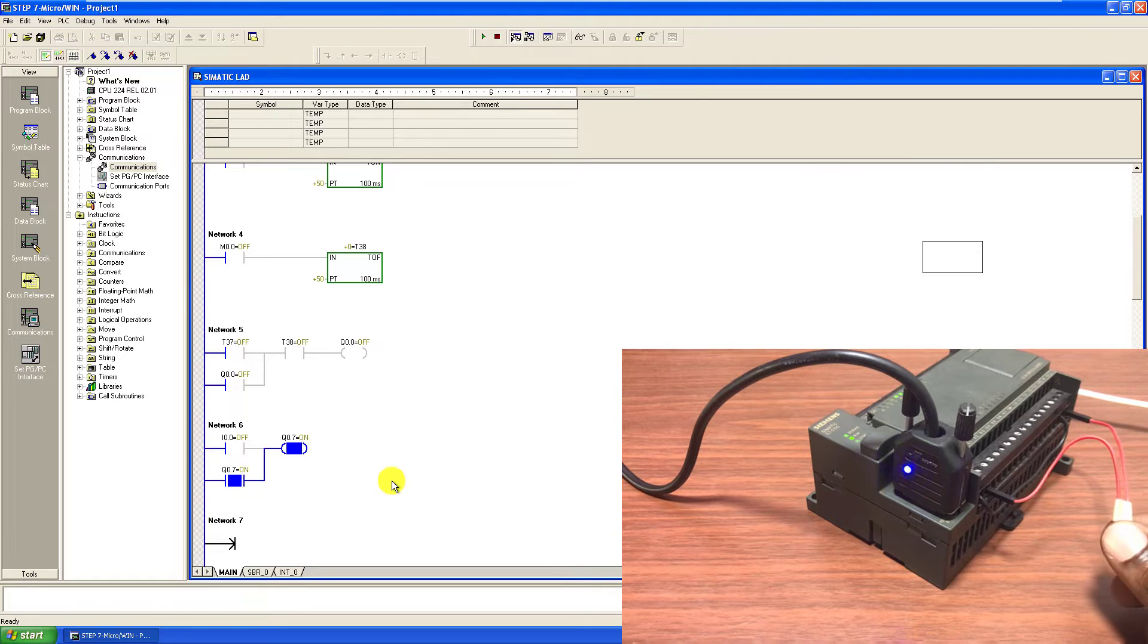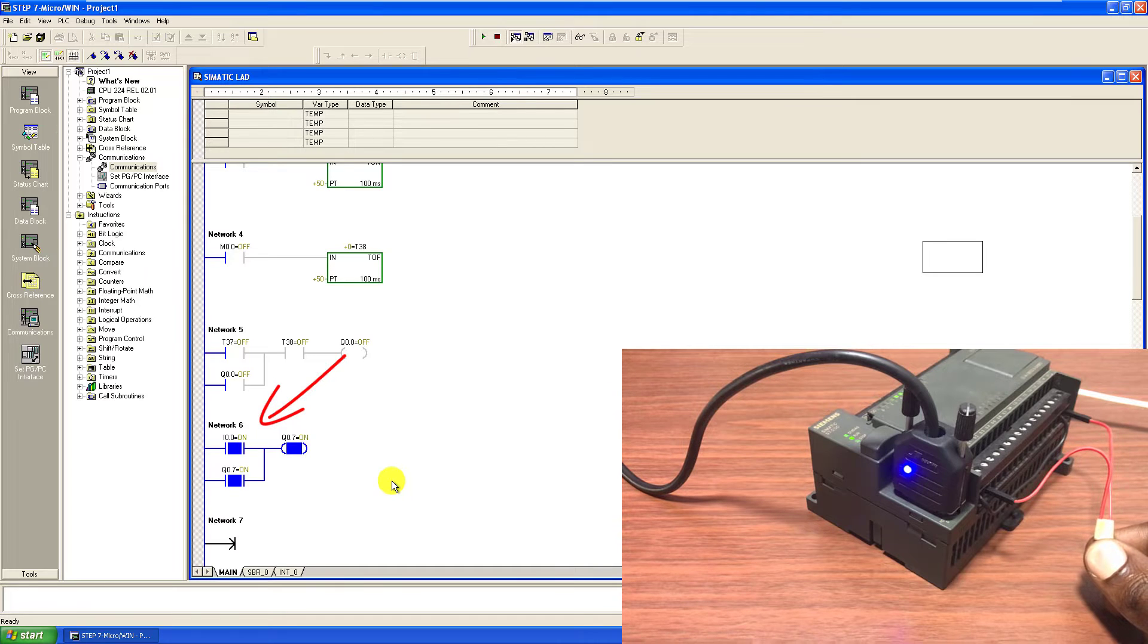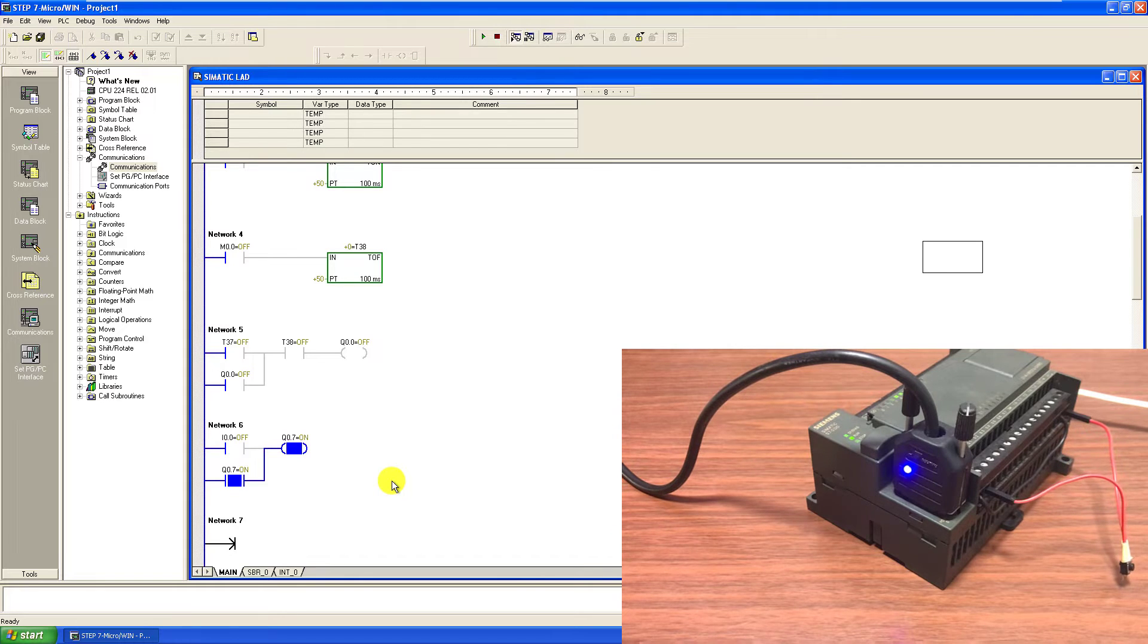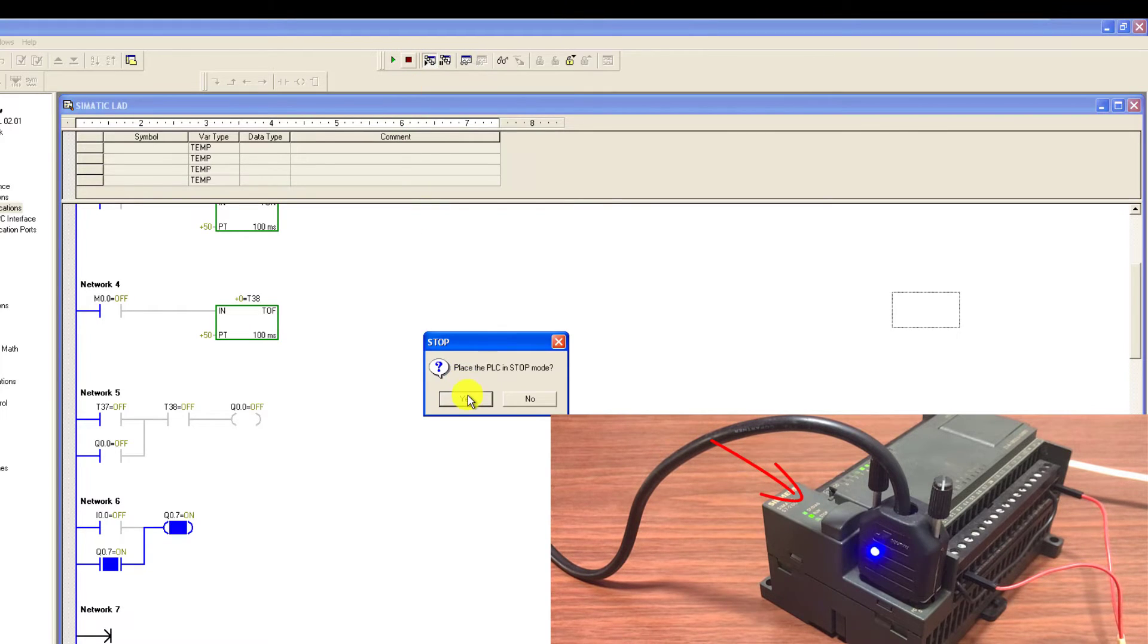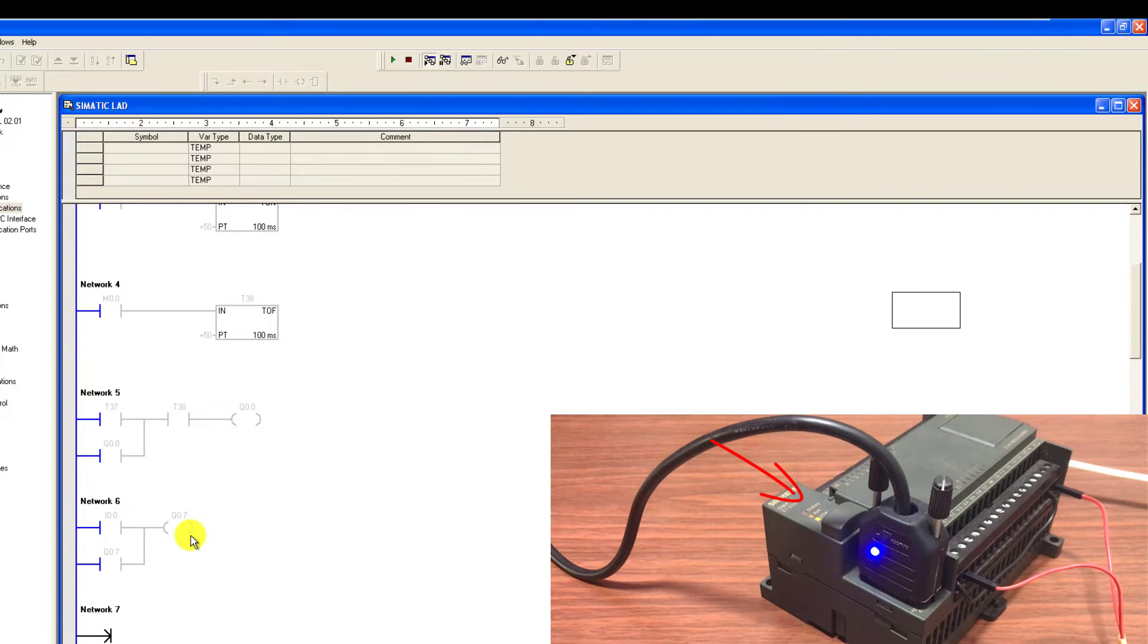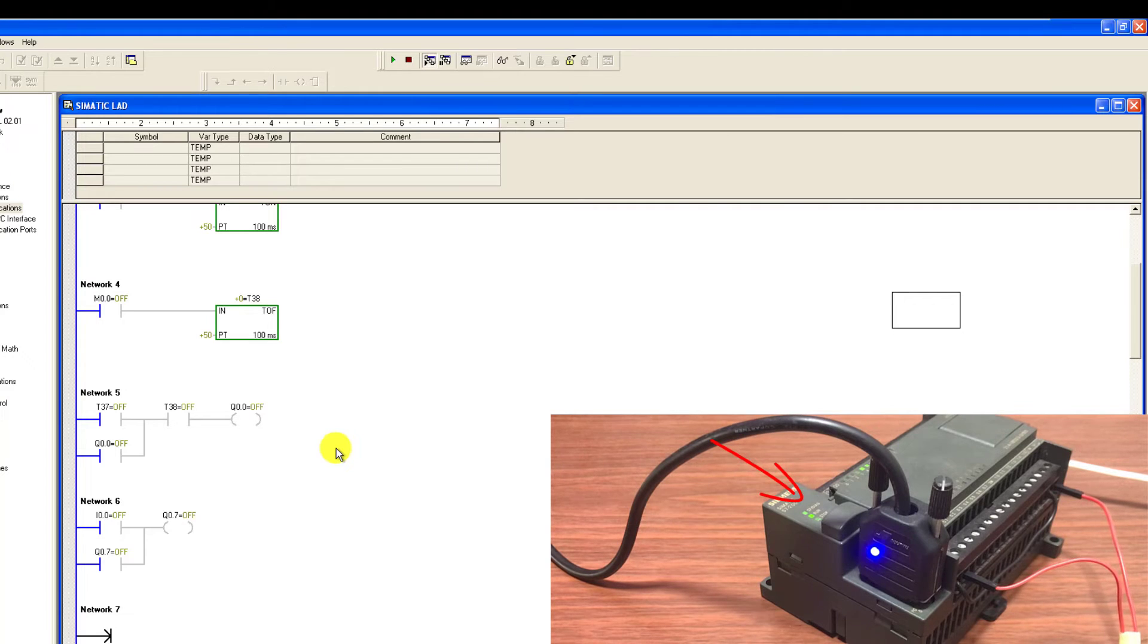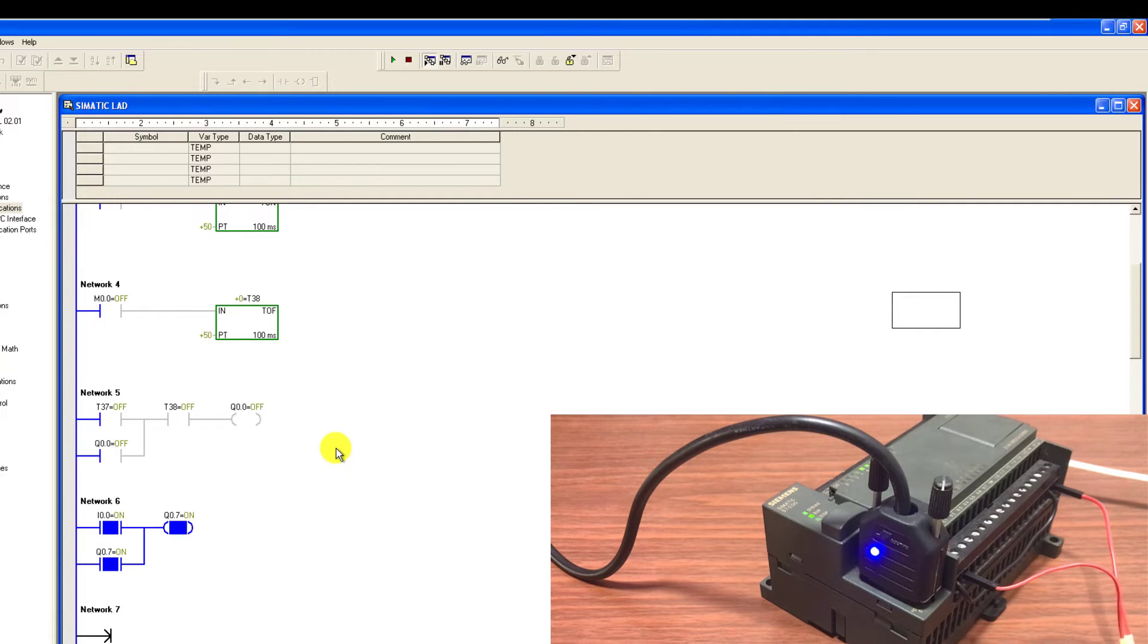And now press the button for test. And then we can see that the button indication is being seen within our software. Working perfectly. And now put the PLC into stop mode on the software. And we can see that the PLC is now in stop mode. Working perfectly. And now try and start the PLC from the software. And we can see the PLC is in run mode. Now press on the button. We can see that this section of the code is activated. And we can see the activity of the button.